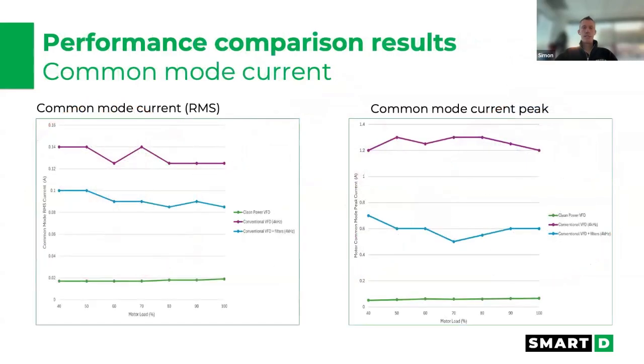And kind of case in point, we go back to the lab, same setup. You can see the level of common mode current with just your drive. And even putting a sine wave filter is not addressing this, because your sine wave filter is just getting some of the common mode current to go through that filter, but it's still reaching your motor. And so with the clean power VFD, I can't say you're eliminating everything, but you're taking out 95% of that common mode current so that you don't have that issue.